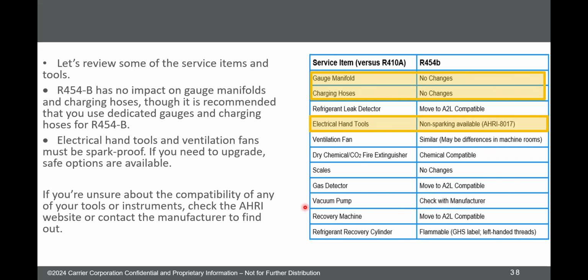What I would have been telling everyone to do is just take the model number of your piece of equipment, go to that manufacturer's website, and they will either have a list by model number of all the things that are compatible, or they won't have that. And you'll go look up the thing that you own, whatever model number that is, and read the spec sheet for it, and it'll tell you what refrigerants are allowed to be used on it. Right, and find it one way or the other that way to see if what you already own is good. And you might not have to buy a ton of new tools.